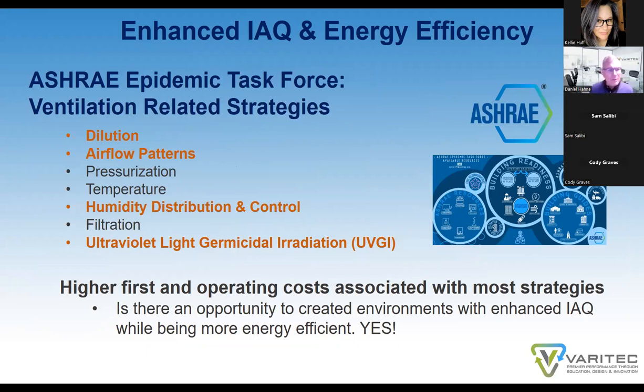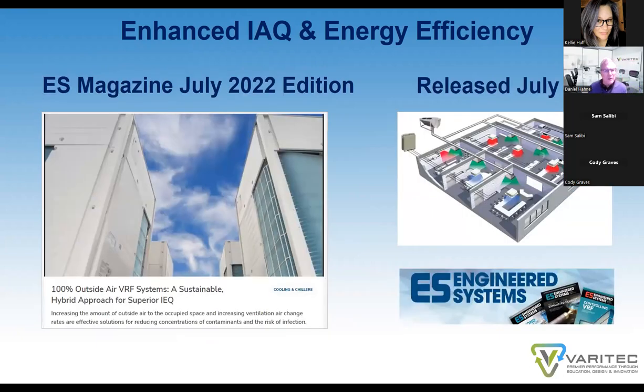Again, to review, ASHRAE's Epidemic Task Force recommends dilution, airflow patterns, humidity distribution and control, and ultraviolet germicidal irradiation as solutions for creating better IAQ and reducing the risk of infection. So is there an opportunity to bridge the divide, to create a building and an HVAC system that will offer both solutions? Well, that was what motivated my July 2022 article for Engineered Systems Magazine, when I evaluated how 100% outside air variable refrigerant systems could be a good hybrid solution for creating better IAQ by guaranteeing the appropriate volume of outdoor air is brought to each building zone, each room, as well as effectively distributing the refrigerant flow to each space to respond to each zone's load.